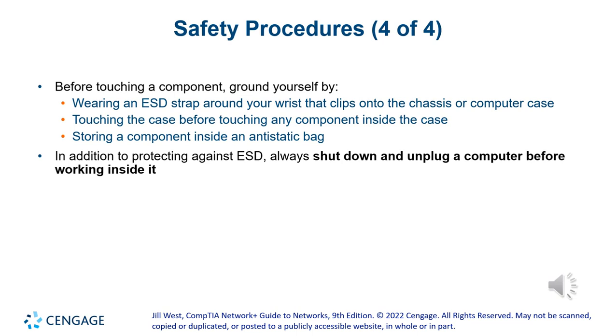But grounding is important. FIU, Florida International University, at one point had some problems with their access points. Some of the wireless access points would get fried all the time, and that was because the pipes they used to run the wires to connect to the network were plastic, and that would not provide proper grounding, because here at the college we do it with metal pipes, and those pipes are actually grounded.